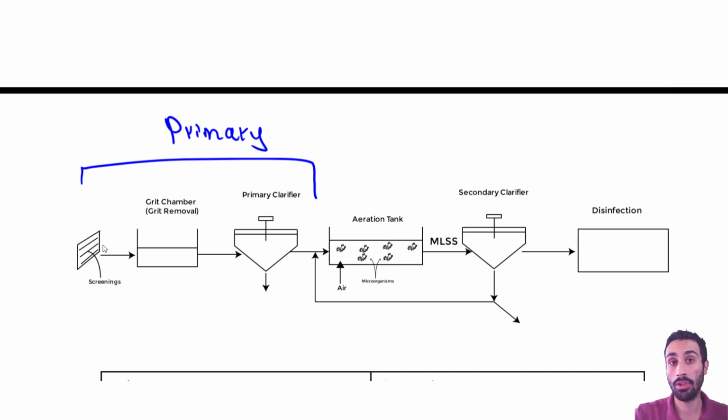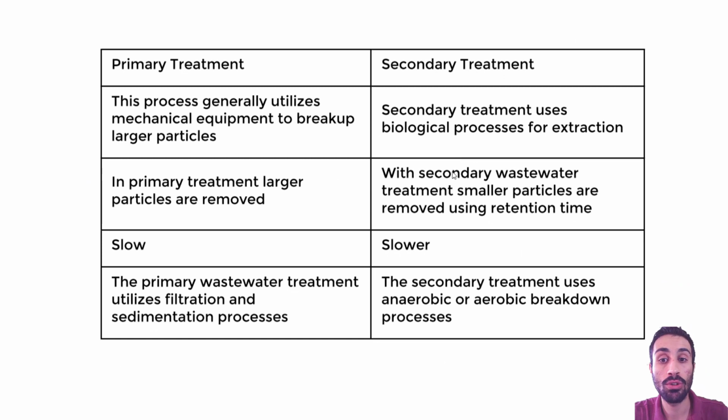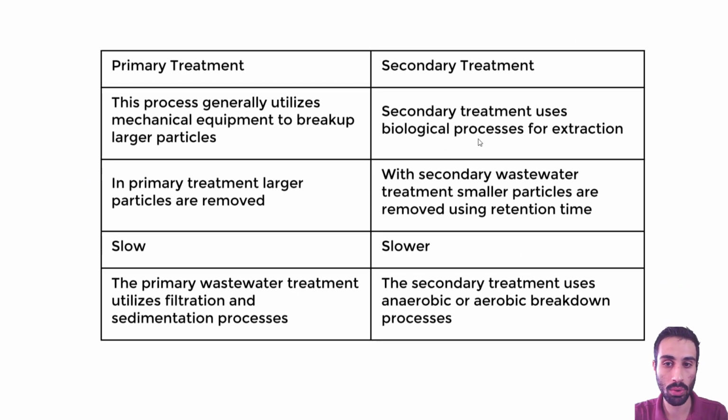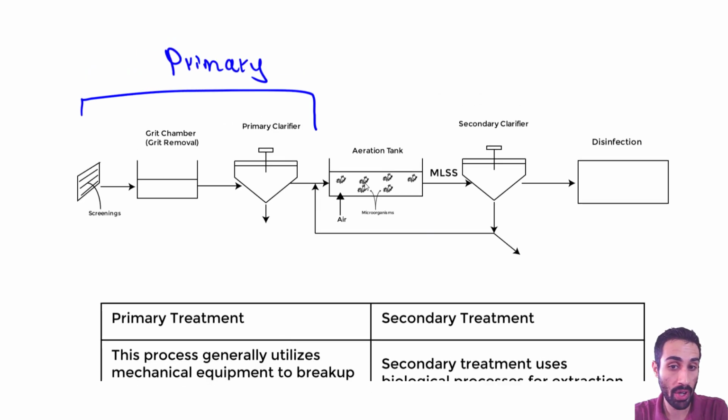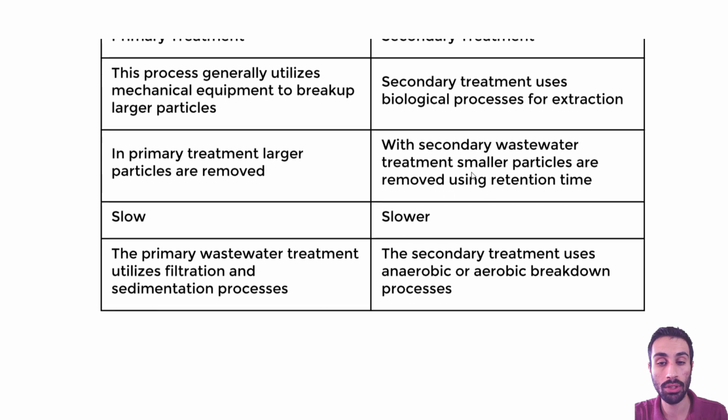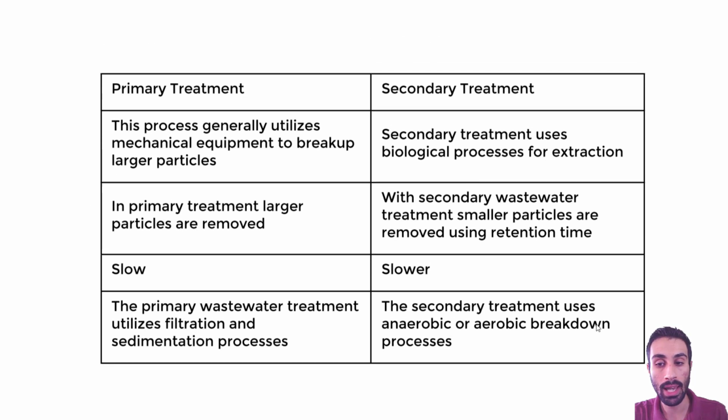Then what comes after primary is secondary treatment, which is your biological treatment. It uses biological processes for extraction, and we remove BOD through the microorganisms, which do the job of breaking down BOD. We know it uses both anaerobic breakdown, without oxygen, and aerobic breakdown processes as well.